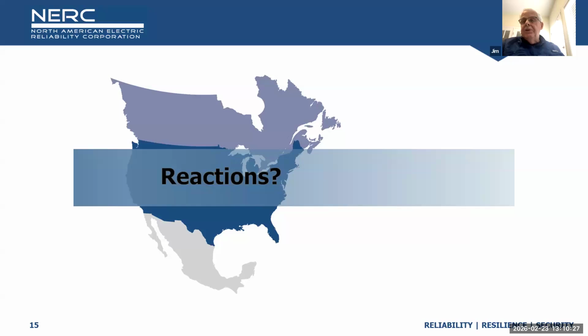That's a similar type of cliff that we've dealt with for years. When the frequency goes down to 57.5 hertz, all the steam units are going to trip due to turbine issues. So I think we do have to get away from a capacity-driven model to a variable, fast-response energy market design. That's interesting, I have to give that some thought — see how the design of the system would change.